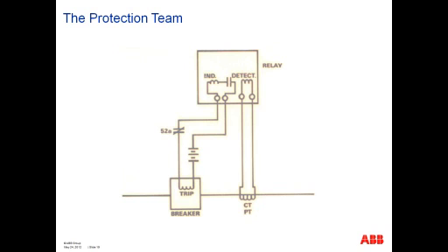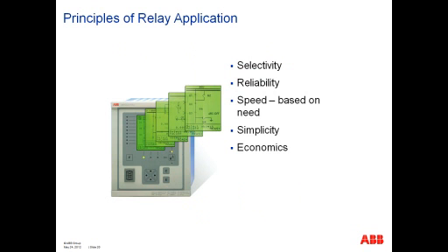Okay, and a simple interconnection here is that you have your CTs on the primary system, your relay, you do some detection, and you have a battery source and a breaker to control. Well, let's talk a little bit about the principles of relay application.